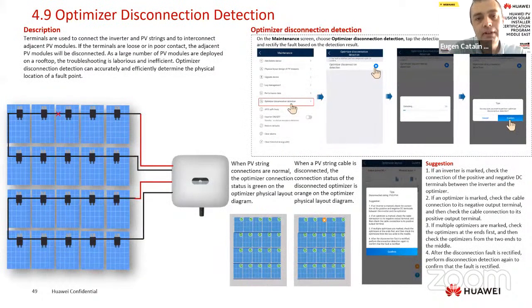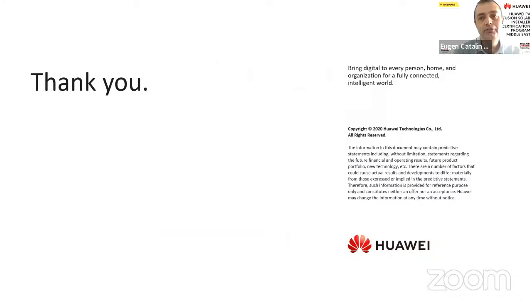We have now a new function with the new optimizer. The function is optimizer disconnection detection. It is there in maintenance, and you can perform this function to check where your problem with disconnecting is. Yes, these locations are disconnected, so you go directly there. Of course, this position will also be according to the layout and so on. You can test this when you have a faulty or disconnected optimizer during your installation. This was my presentation.